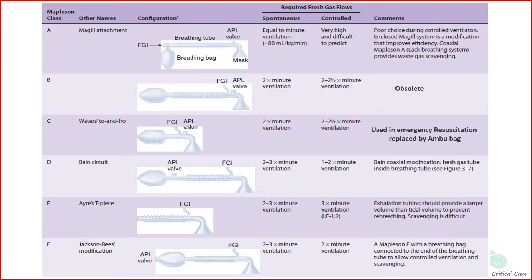Mapleson D, E, and F require higher fresh gas flow to prevent re-breathing. They are next in order of preference for spontaneous respiration, but they are better than Mapleson A for controlled ventilation.